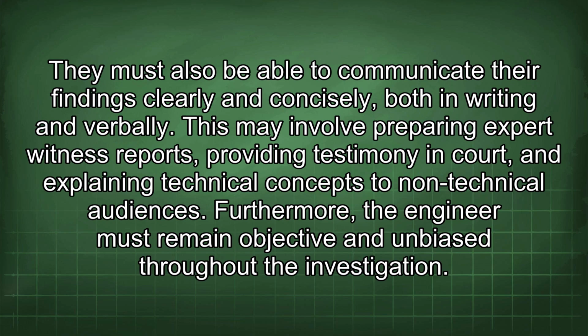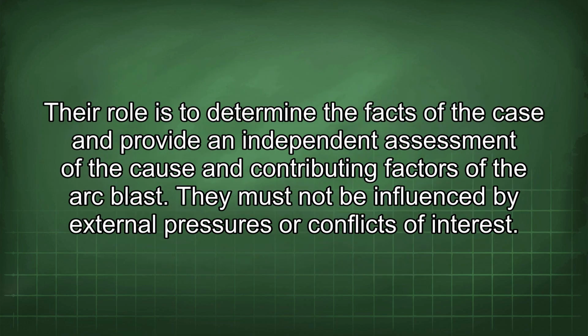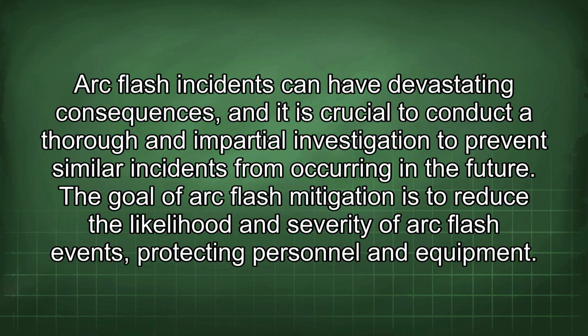This may involve preparing expert witness reports, providing testimony in court, and explaining technical concepts to non-technical audiences. Furthermore, the engineer must remain objective and unbiased throughout the investigation. Their role is to determine the facts of the case and provide an independent assessment of the cause and contributing factors of the arc blast. They must not be influenced by external pressures or conflicts of interest. Arc flash incidents can have devastating consequences, and it is crucial to conduct a thorough and impartial investigation to prevent similar incidents from occurring in the future.